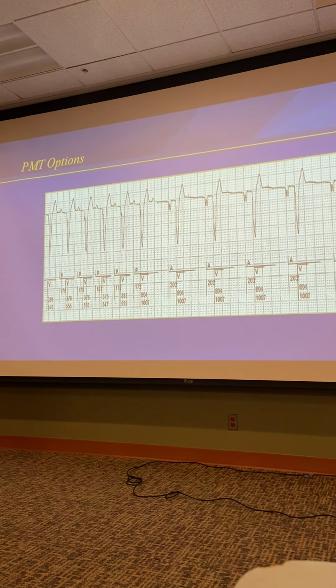This is an example of how the device will terminate the rhythm itself. This is a pacemaker-mediated tachycardia. The R wave is actually preceding the P wave. It's been sustained. The device recognizes it after 10 beats. It extends that refractory period. This P wave can no longer get back up through the system, and a normal rhythm is restored. And it should do that all on its own.